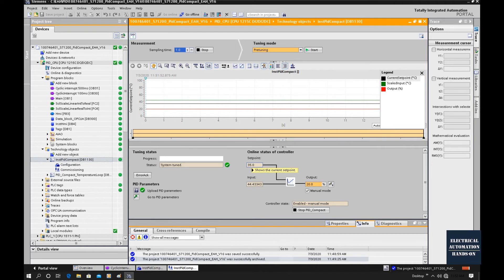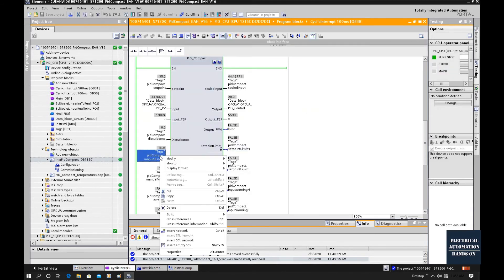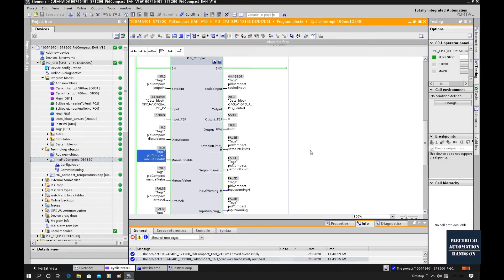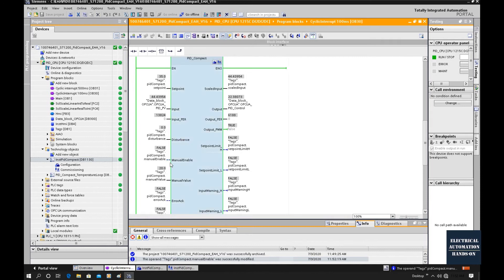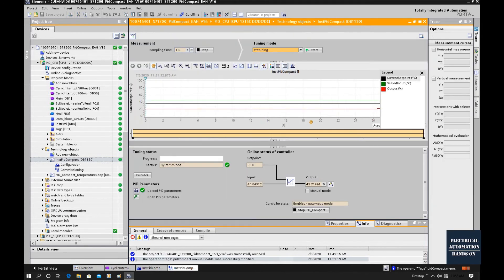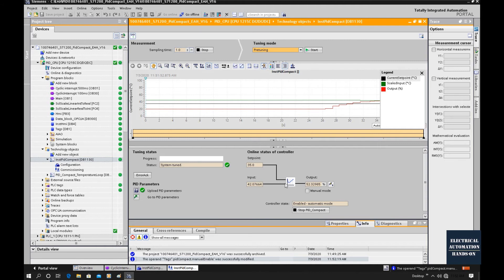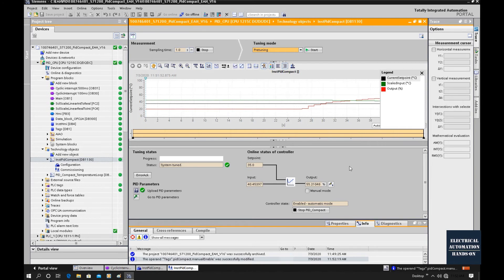I'm going to switch the system into automatic mode. Go back to the program and I will switch off manual. So the system will switch to automatic mode. Hit this button. Go back to the commissioning window. We will see the temperature is going down. That means the PID is working. Because our setpoint is 35, the process value decreased from 45 to 35.